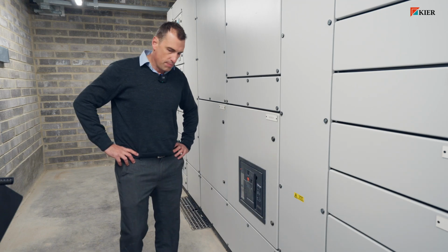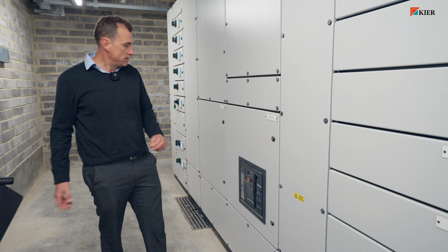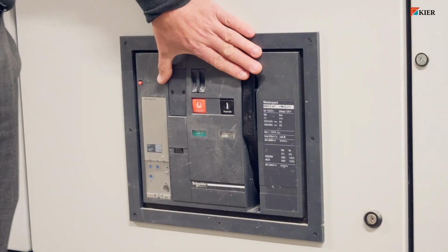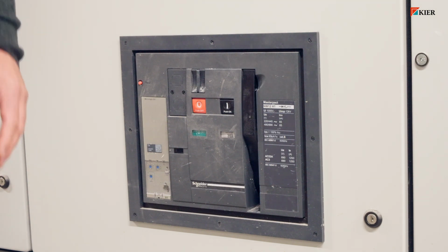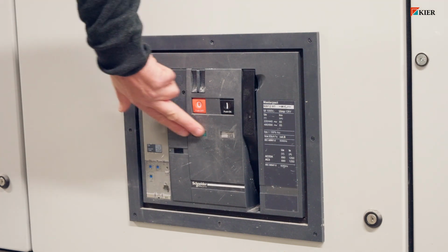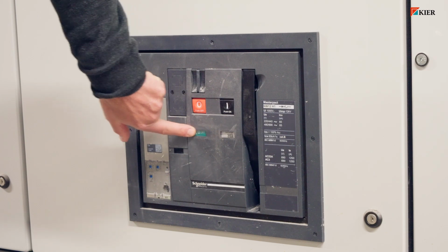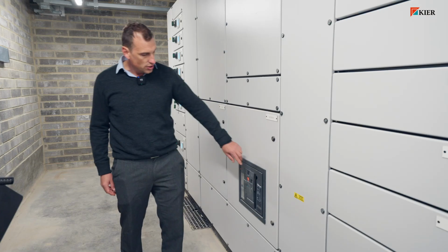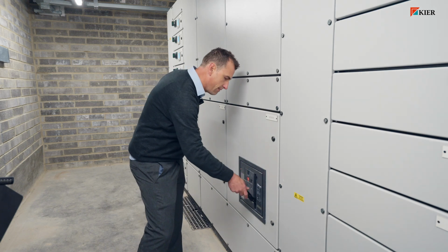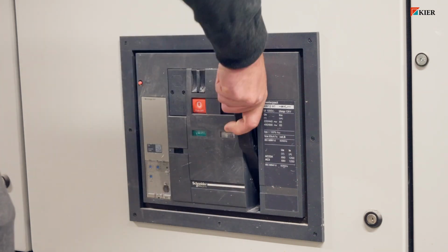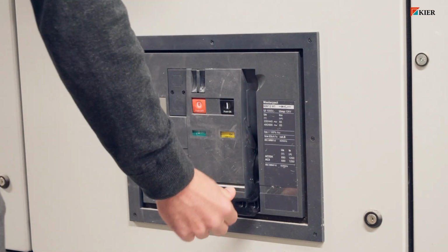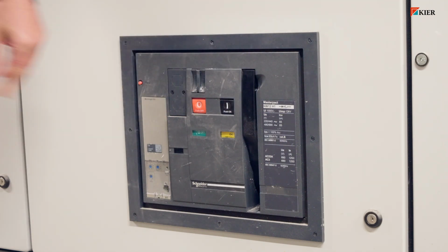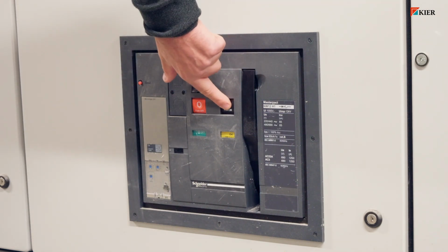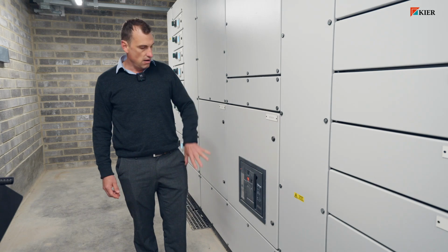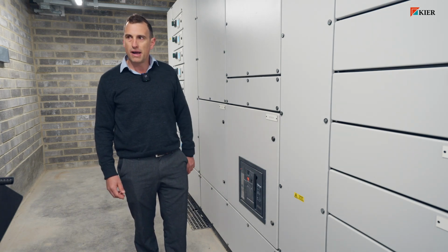In the event of a building's mains failure, the first point to come and investigate will be your main incoming ACB. Obviously, if there is a failure, it will be tripped. So you'll look at it, and it will indicate that it's off. In order to recharge it, you would obviously use this lever, recharge it until you hear it click. There, that is showing that it's now energized and ready to go. And then you just press the on button and that locks. So now that is recharged, and that should bring your power back onto the building.